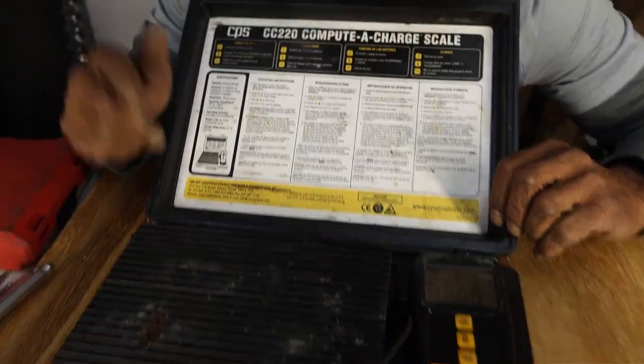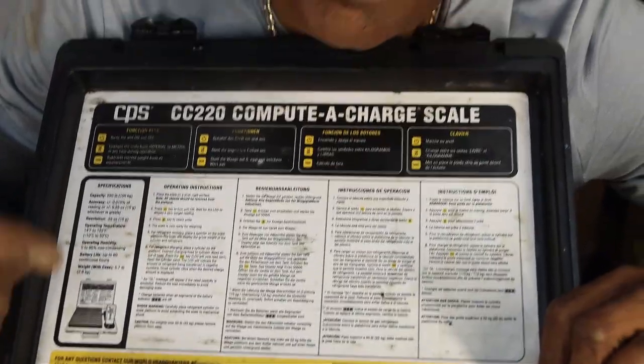It's a charging tool for mostly commercial systems, but it's now moving into residential systems. When you do a change out, sometimes you need to look at the data plate on the unit and it'll tell you what the factory charge is, and that's how much Freon you want to put in the system. But we're going to teach you to charge by superheat, by subcooling, and one other method that I'll show you rather than tell you about. We're going to understand all the different ways of charging a system. I'm going to give you all that you need.